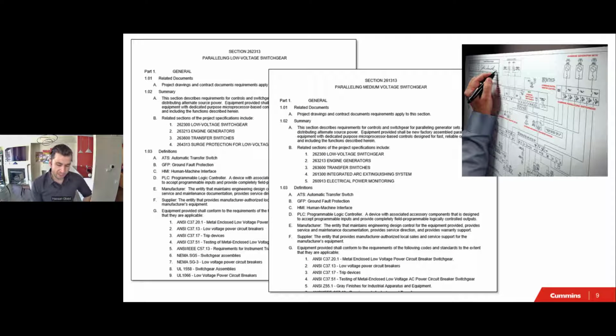So when you're designing your system, you're specifying, and the specification that you use is section 2600 in the master spec, named paralleling switchgear, and it could be medium voltage or low voltage, and you write anywhere between 20 to 30 to 35 pages of specification. I would love for us to dive into every single line item, but we don't have time. It's going to take us a week to do all that. But I'm going to cover 1 or 2, or about 3 slides about traditional paralleling and traditional specifications and how we specify paralleling systems today.